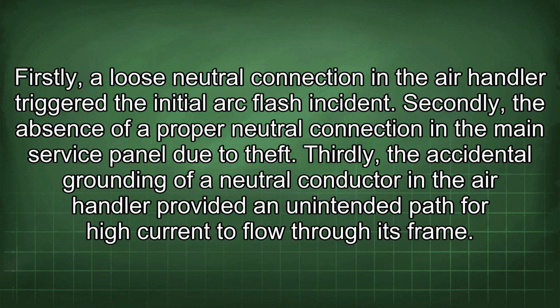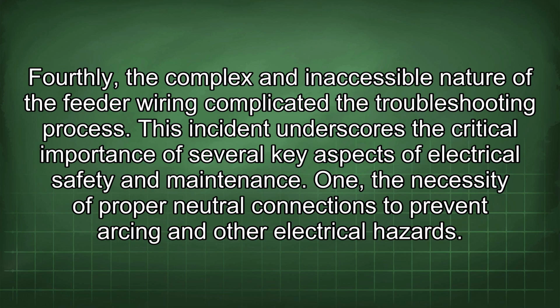Firstly, a loose neutral connection in the air handler triggered the initial arc flash incident. Secondly, the absence of a proper neutral connection in the main service panel due to theft. Thirdly, the accidental grounding of a neutral conductor in the air handler provided an unintended path for high current to flow through its frame. Fourthly, the complex and inaccessible nature of the feeder wiring complicated the troubleshooting process.